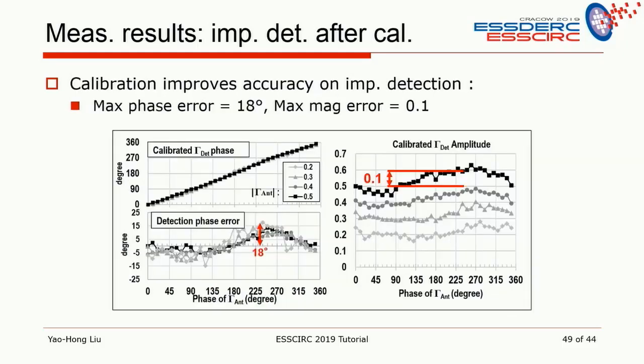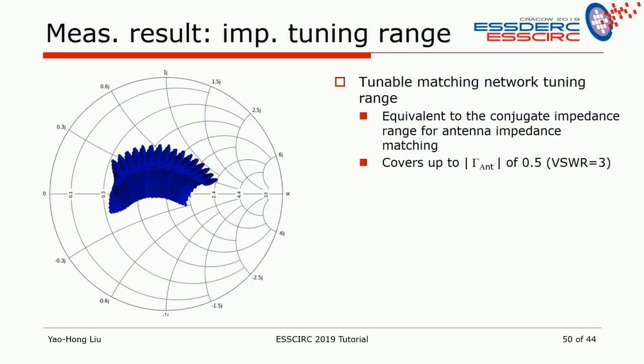Once we do the calibration, we tune this phase mismatch and this transformation. We are able to match this 0 degree of antenna impedance to the same 0 degree here. So with this, we can know the antenna impedance through this measurement. Here's the coverage in the Smith chart. If we tune this matching network, we are able to cover this area, which corresponds to a VSWR of 3. That is already quite sufficient coverage for a typical case where you put the antenna in contact with your body.